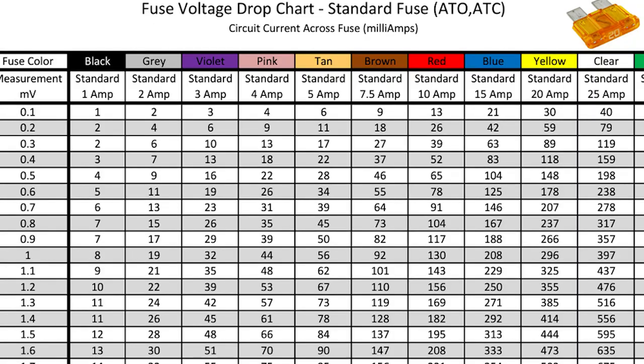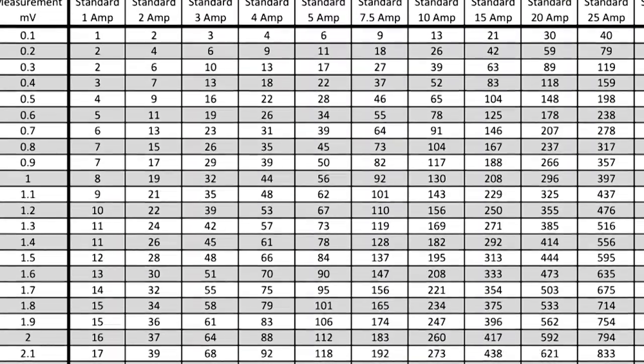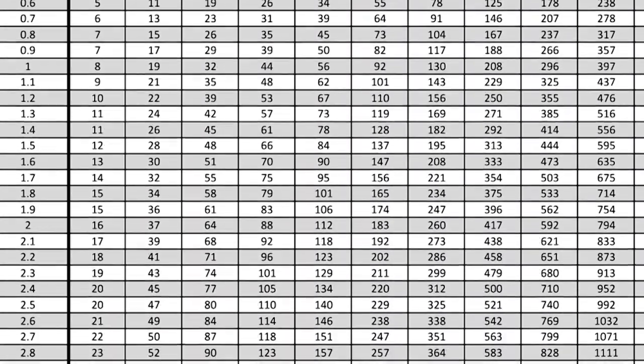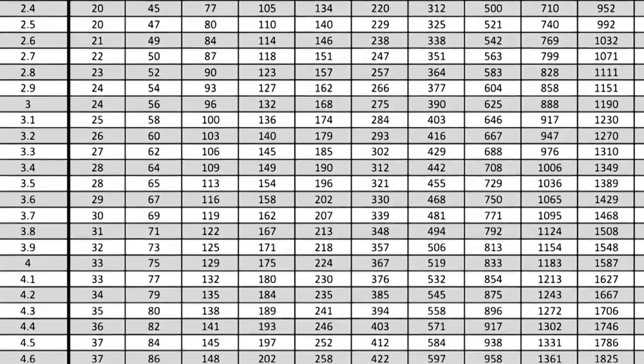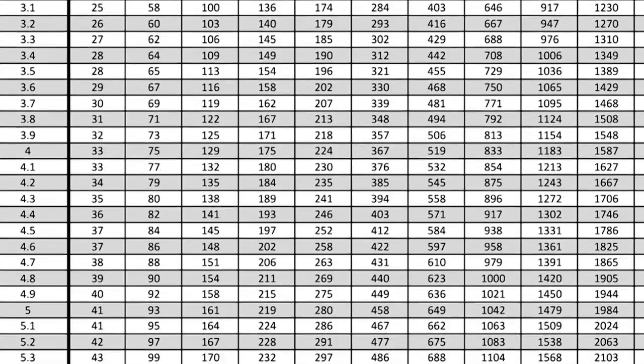You have to convert the voltage measurement to current using any of the numerous conversion charts available on the internet before you could conclude that the current draw was excessive or just part of a bigger problem. Most importantly, it's easy to miss an intermittent problem. Unless you're measuring drop across the fuse at the exact moment the draw is occurring, you can see it would be very easy to miss that circuit and overlook it as the cause.